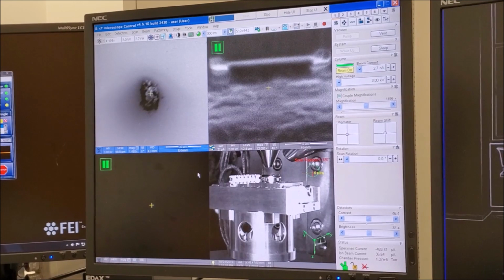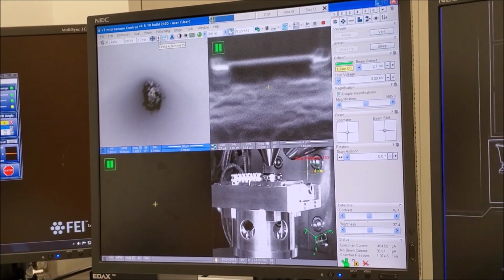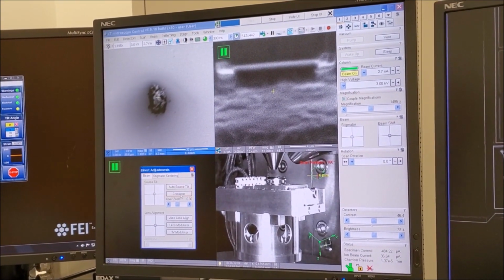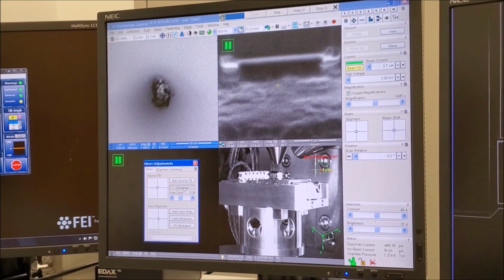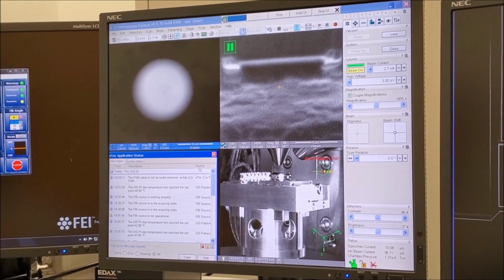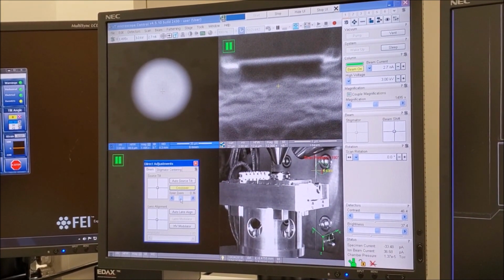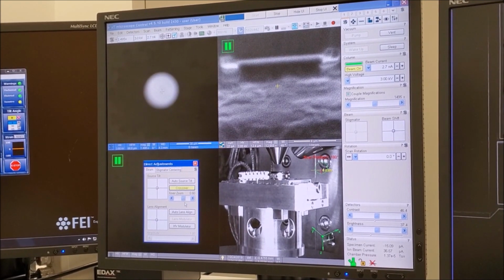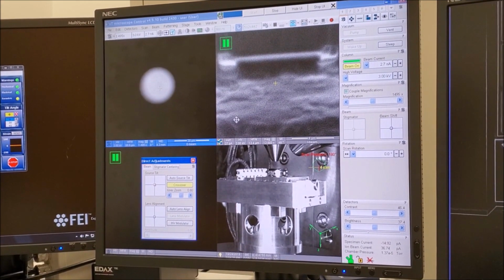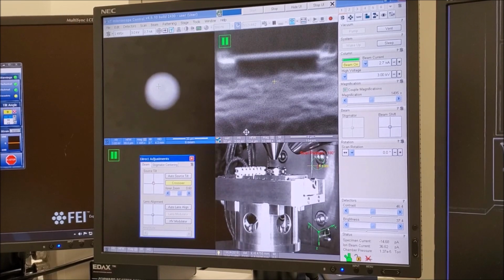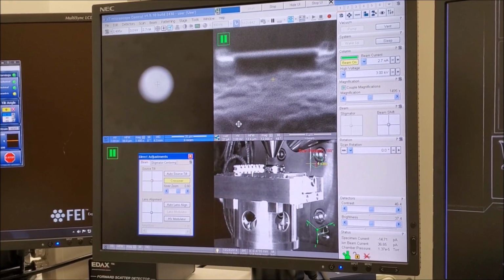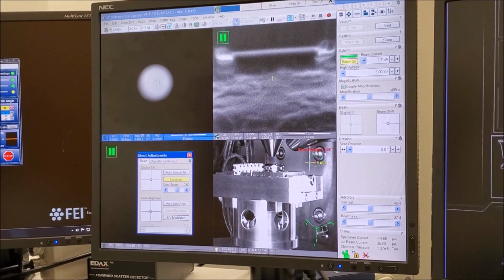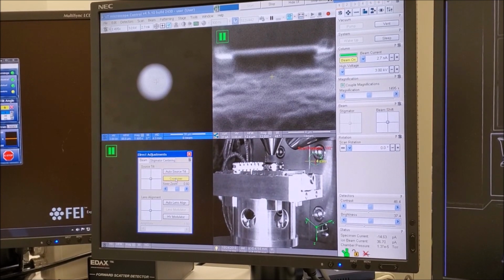With the sample at eccentric height and the stage tilt at 0, the electron beam can now be aligned. Select Direct Alignments from the toolbar. In the Direct Alignments dialog box, select Crossover to enter crossover mode. Then use the crosshairs under Source Tilt to align the spot so it is centered in the image. Then select Crossover to return to image mode when complete.